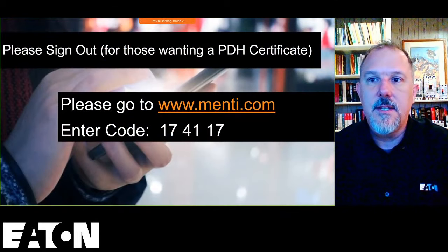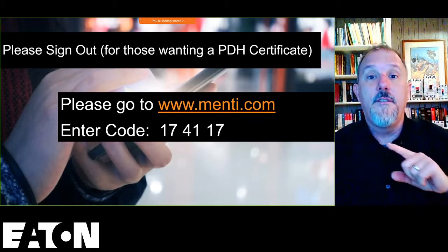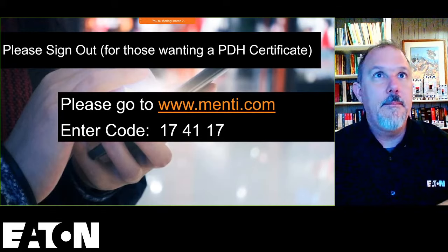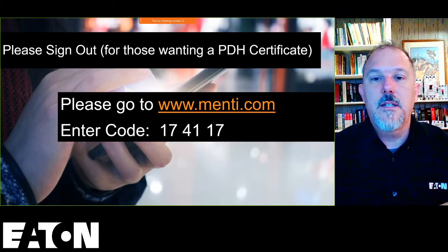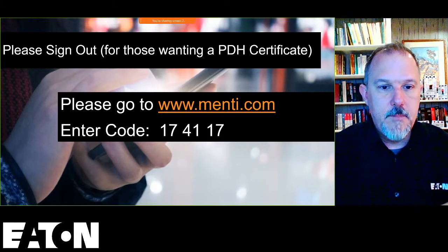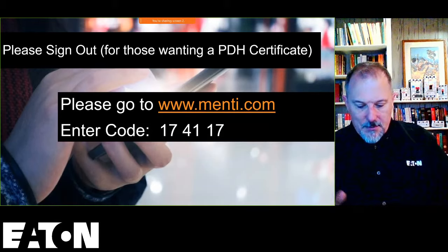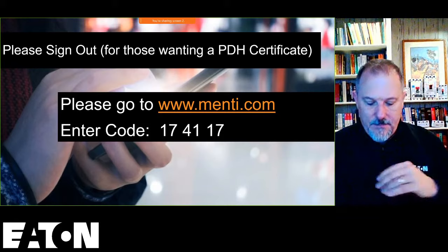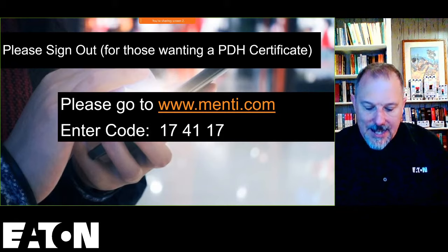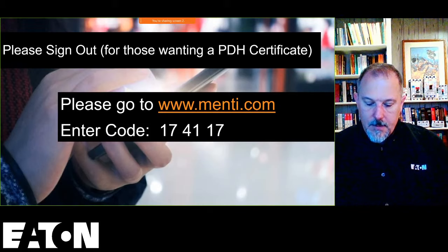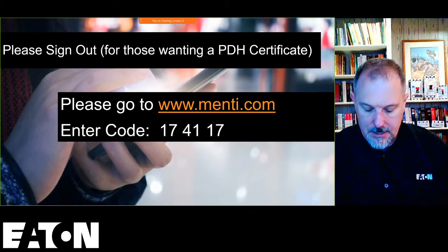But I want to continue this discussion because I'm looking at 440.4, and I'm telling you, it's confusing. It is absolutely confusing. It tells the manufacturer that they must do the math. So what does it tell him, though? It says that the minimum circuit ampacity has to be marked on there, right? But it says the ampacity shall be calculated.